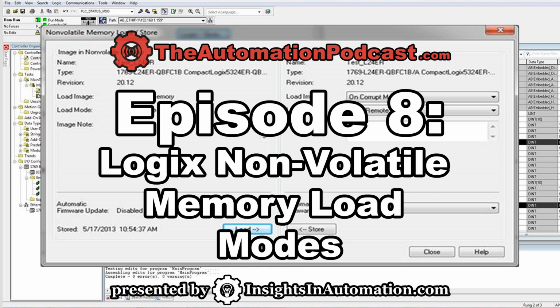Now, user-initiated is pretty self-explanatory. The only way that's going to load from non-volatile memory is if you initiate it manually yourself using RSLogix 5000. The next mode, on power-up, means that every time you cycle power to the PLC, it's going to load from non-volatile memory. Now, that's not always good if your operator has entered a bunch of parameters on an HMI somewhere, and then every time you cycle power to the machine, those disappear because it's loading from non-volatile memory. He's not going to be very happy. So we don't often use the on power-up mode.